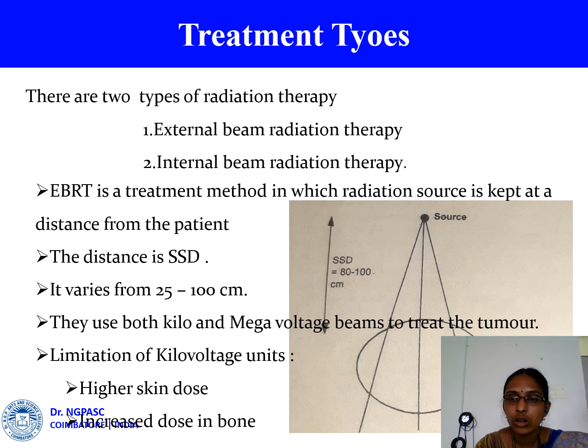These megavoltage beams are produced either by a cobalt-60 machine or a modern linear accelerator. In a cobalt-60 machine, the radiation is produced by the radioactive element cobalt-60. Cobalt-60 emits gamma photons having an average energy of 1.25 MeV. In a cobalt-60 machine, they usually use 80 centimeters as the SSD.